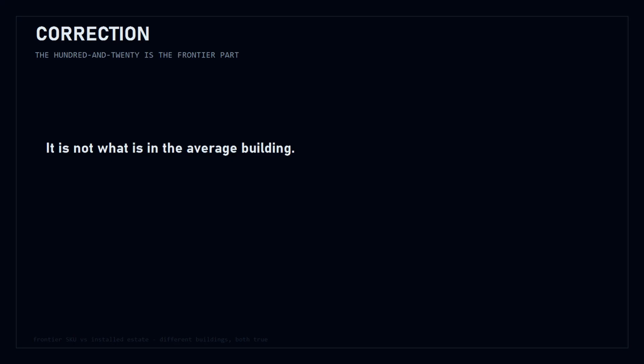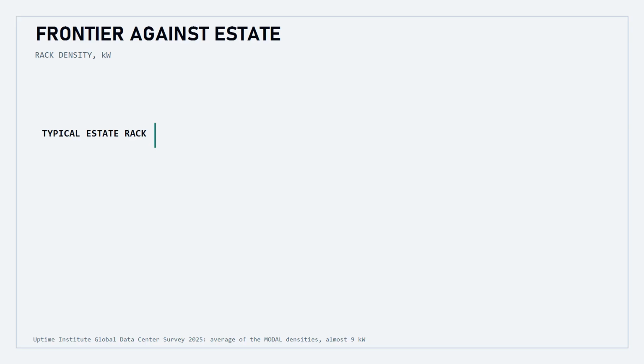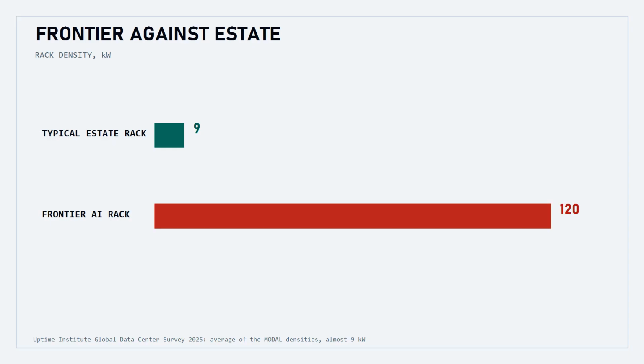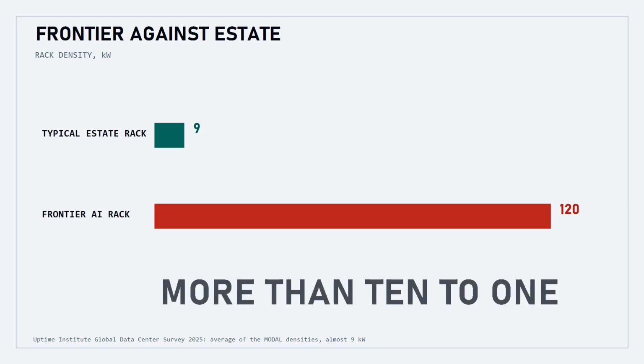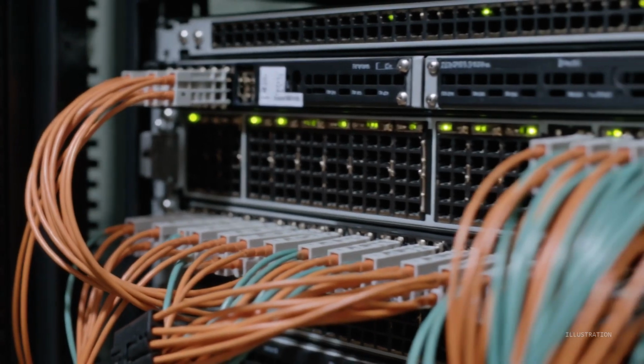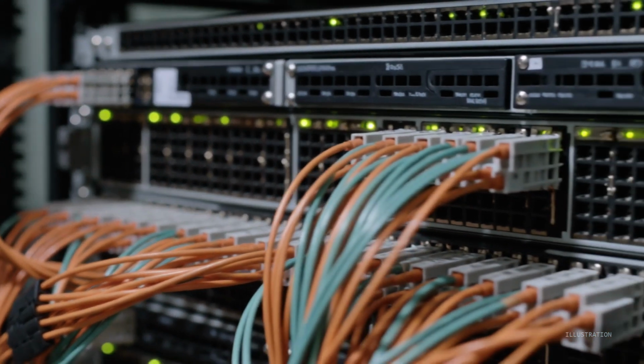Here is the first thing worth correcting. That 120 kilowatt figure is the frontier part. It is not what is in the average building. Uptime Institute's 2025 survey puts the typical rack density around 9 kilowatts. The gap between the headline and the estate is more than 10 to 1. Both numbers are true. They describe different buildings. Anyone quoting one without the other is selling you something. But the frontier is where the engineering breaks, so that is where we go.